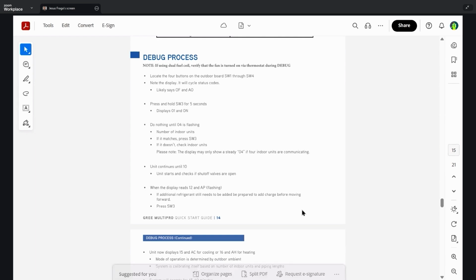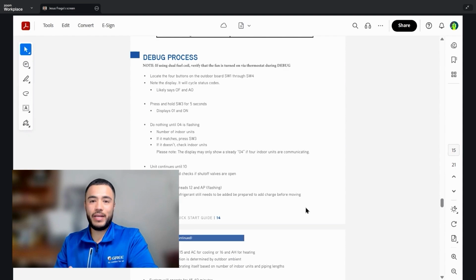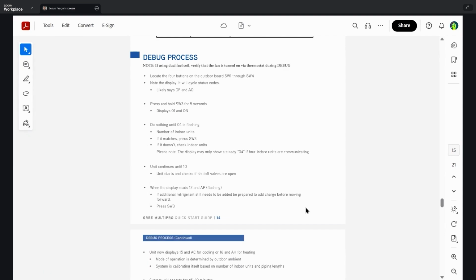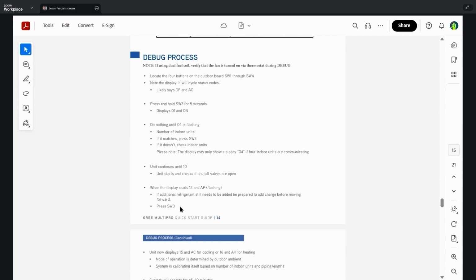That error code needs to be referenced back to the service manual to see exactly what that is, or on the back of the service panel, which will tell you what that error code means. Usually when you get an error code, it means that there's something that went on with the installation, whether it's communication wire, whether it's maybe power to the indoor units, and so on and so forth. So just depending on what kind of error code you're getting at the outdoor unit will indicate what is actually wrong with the system. And once all those errors are corrected, if you have any, you should be able to easily go through this debug process and have the system fully operational within 40 to 45 minutes.